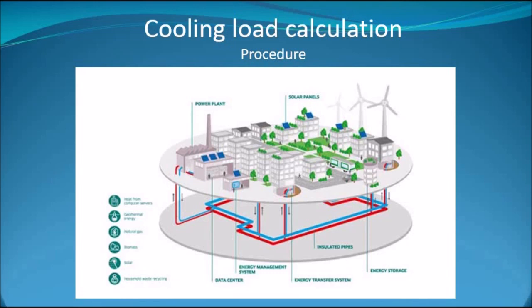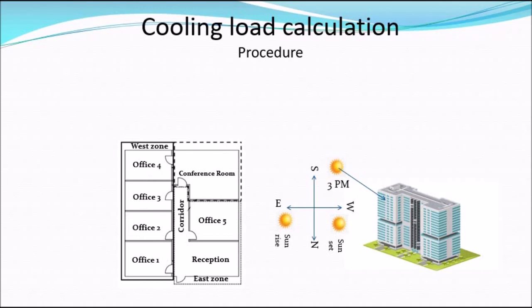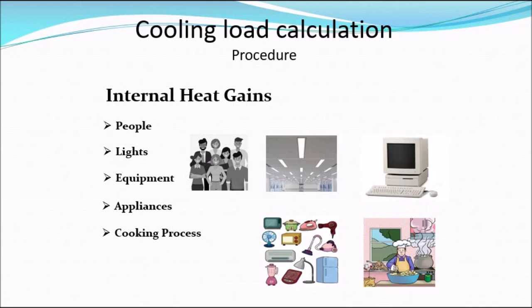We primarily need to obtain the building characteristics such as size, color, shape, location, and orientation — north, south, east, or west. If the building zone is exposed to direct sunlight, the heat transfer will be higher. This is an office building with windows facing east and west, so the cooling load calculation for each orientation will be different.